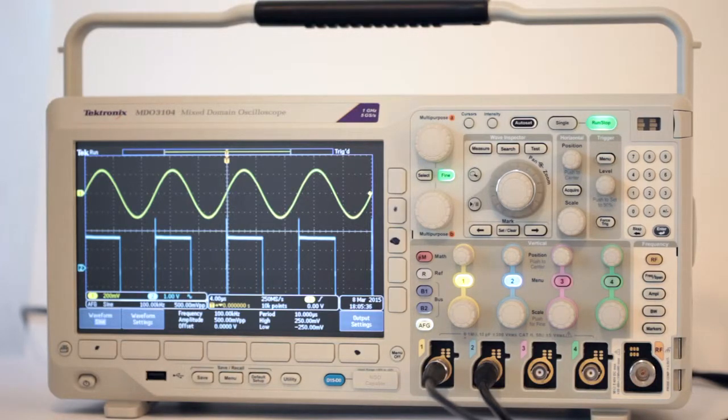For this to happen, if necessary, press Output Settings along the last soft key at the bottom of the screen. Then, along the right side of the screen, press Auxiliary Output. This opens three alternatives. Use multipurpose knob A to select AFG.